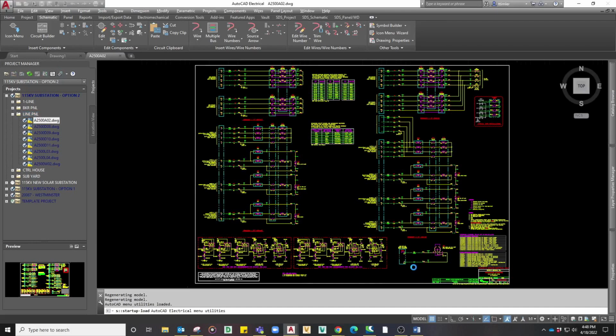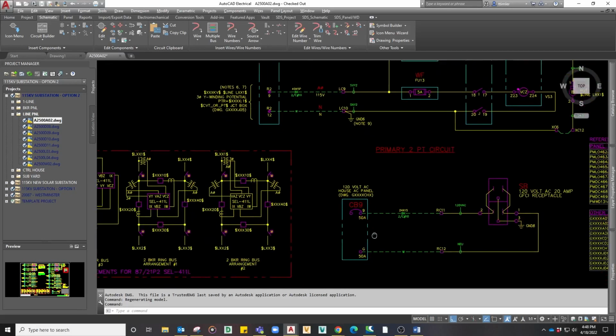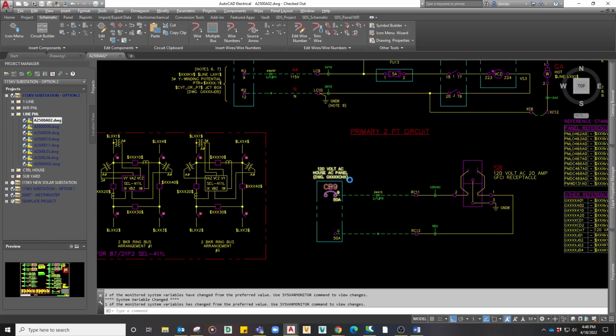Just as in example 1, I'm going to focus on the same AC cable located at the bottom right hand of the drawing. Instead of editing a cable bubble and signal arrows like in example 1, this cable now has a circuit breaker schematic symbol and schematic cable marker symbols to edit. I'll make 2 edits, one to the circuit breaker schematic parent symbol and another to the parent cable marker. The elements for annotation, referencing, and cable wire to from reporting is built right into the same location.